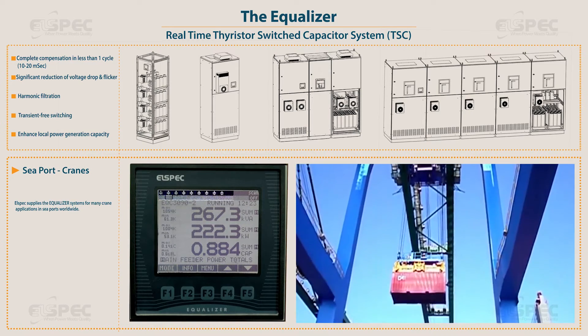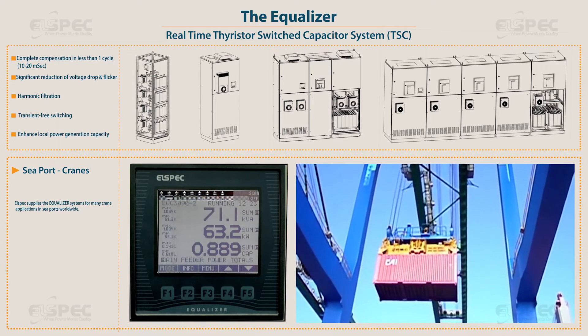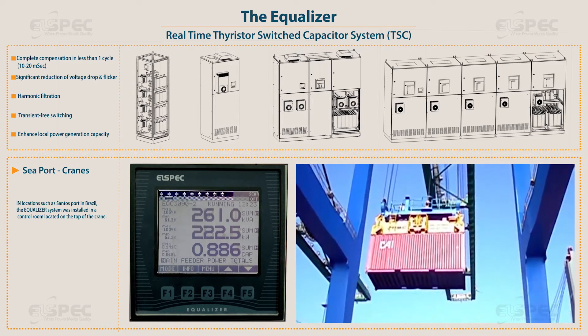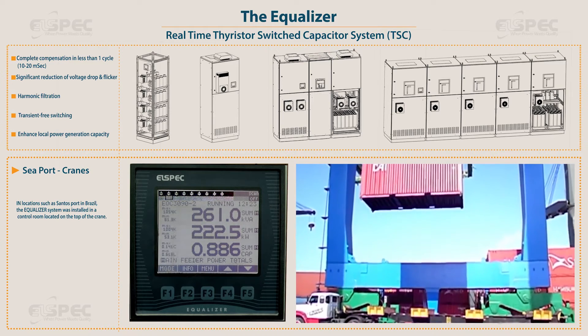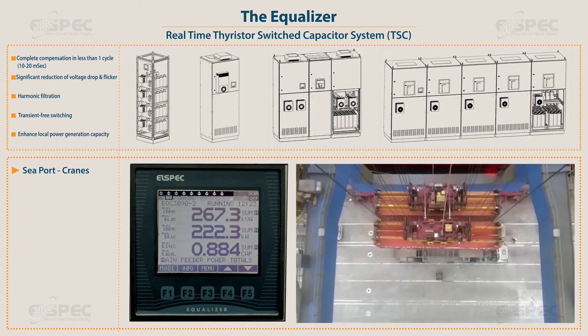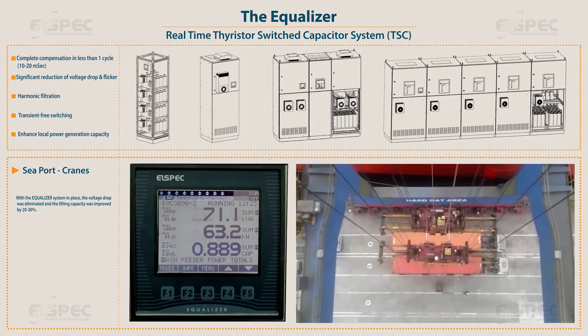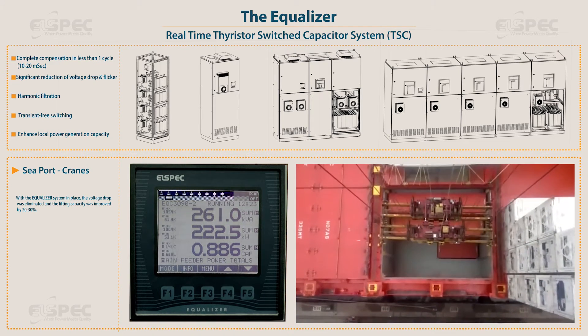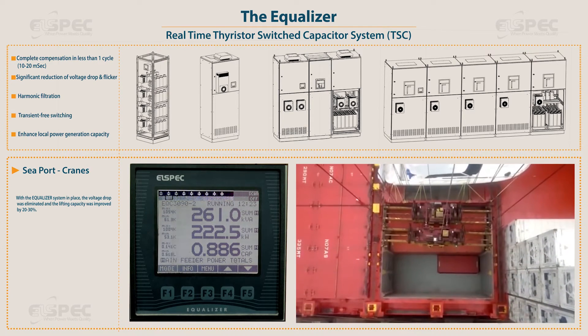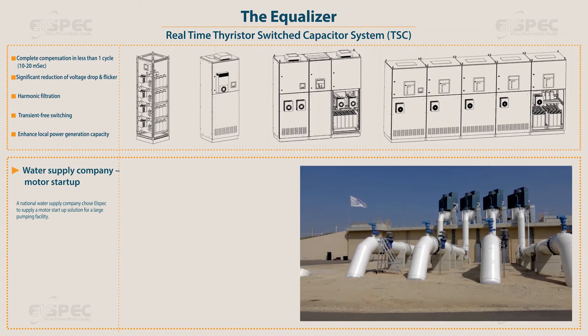Elspec supplies the equalizer systems for many crane applications in seaports worldwide. In locations such as Santos Port in Brazil, the equalizer system was installed in a control room located on the top of the crane. When lifting a container, the consumption of power and reactive energy increases and the voltage drops. With the equalizer system in place, the voltage drop was eliminated and the lifting capacity was improved by 20 to 30%.